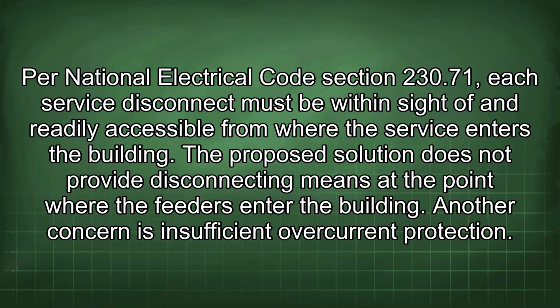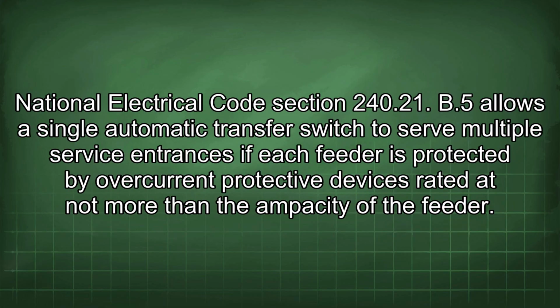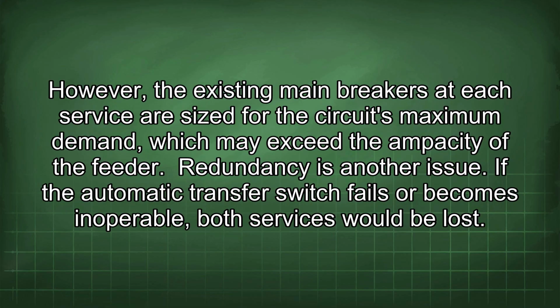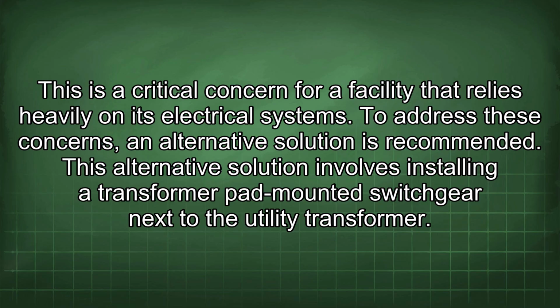Another concern is insufficient overcurrent protection. National Electrical Code Section 240.21(B)(5) allows a single automatic transfer switch to serve multiple service entrances if each feeder is protected by overcurrent protective devices rated at not more than the ampacity of the feeder. However, the existing main breakers at each service are sized for the circuit's maximum demand, which may exceed the ampacity of the feeder. Redundancy is another issue. If the automatic transfer switch fails or becomes inoperable, both services would be lost. This is a critical concern for a facility that relies heavily on its electrical systems.